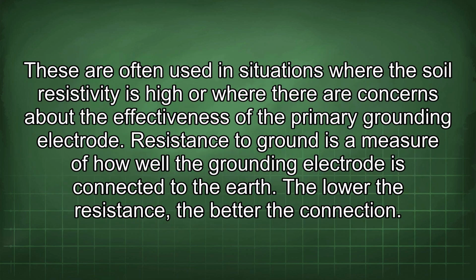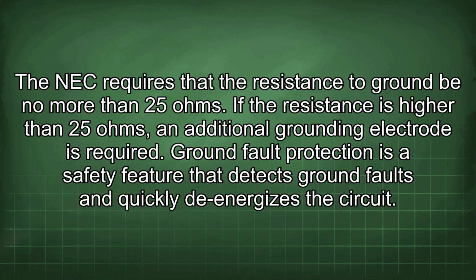These are often used in situations where the soil resistivity is high or where there are concerns about the effectiveness of the primary grounding electrode. Resistance to ground is a measure of how well the grounding electrode is connected to the earth. The lower the resistance, the better the connection. The NEC requires that the resistance to ground be no more than 25 ohms. If the resistance is higher than 25 ohms, an additional grounding electrode is required.